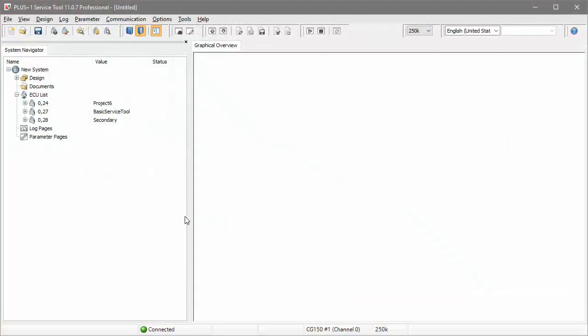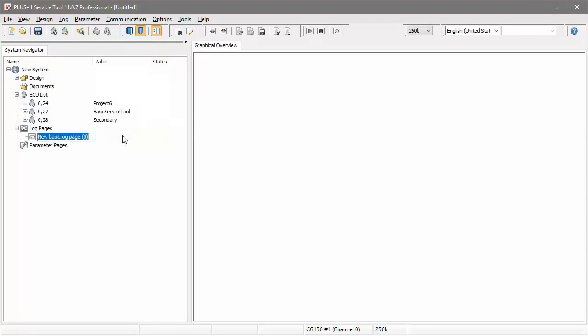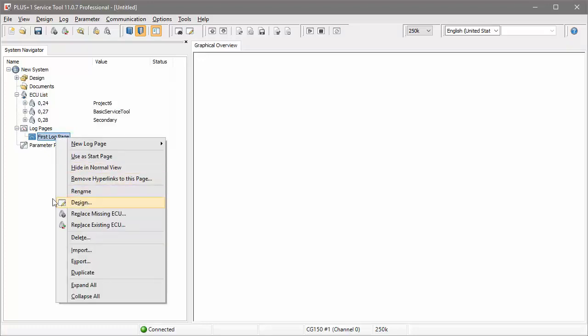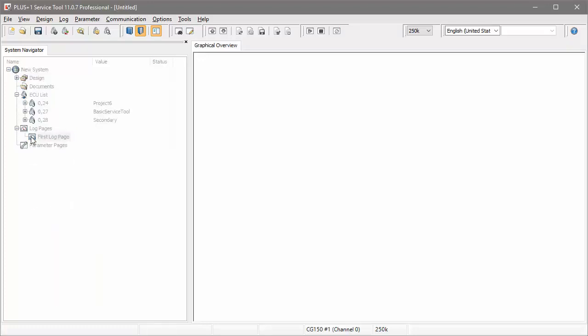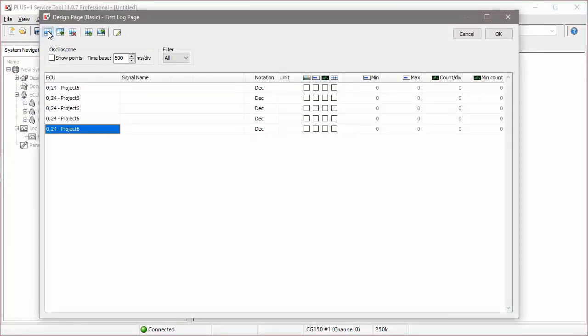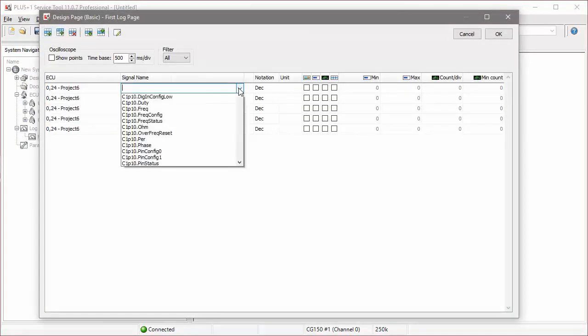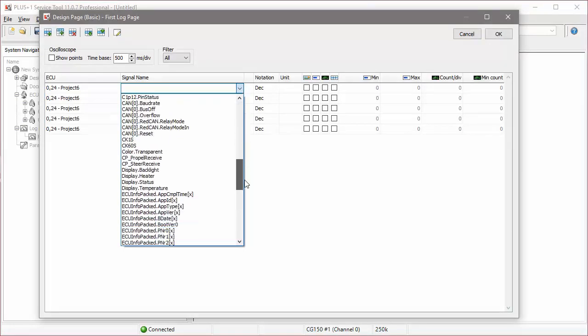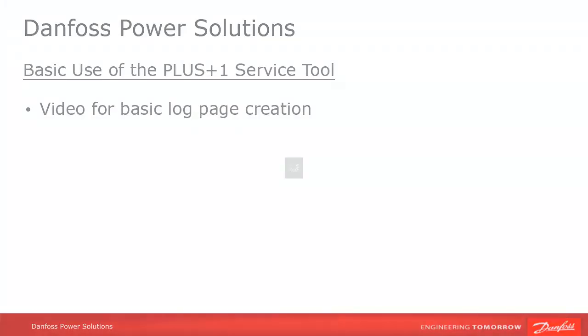Right-click on the Log Pages field and create a new basic page, giving it an appropriate name. Double-click on the page to edit it. Add a row for every signal value that you want to monitor using the icons at the top of the page. You can only monitor 10 signals at a time in a basic log page, but there's no limit on advanced pages.